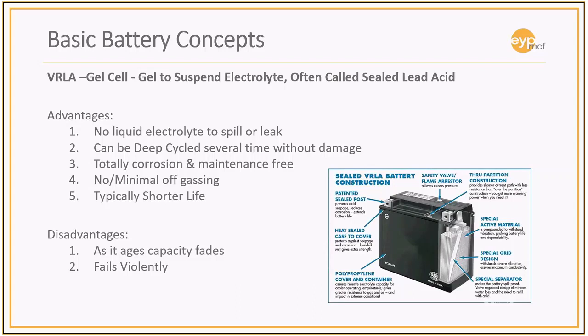One of the things that does typically happen with these jars is that they're placed very close together inside cabinets, and so they tend to get warm. In some cases, we've actually added ventilation to the cabinets to maintain the proper temperatures in the battery cabinets to keep the batteries as long-lived as possible. Some of the disadvantages with these types of batteries are that as they age, the capacity fades, and that's true in any battery, but these tend to age faster. These are available in a 5, 10, and even a 15-year environment.